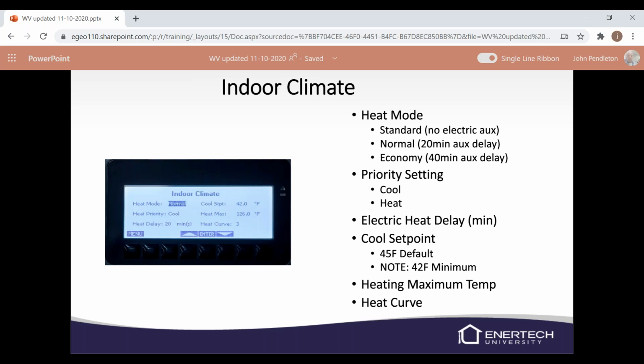You can actually go in there and adjust your electric heat delay to a different setting than those 20 or 40 minutes if you'd like. That's totally up to you. Your cooling set point, I probably wouldn't mess with it too much. 42 is about the minimum we want to see, and we recommend 45. Here you can adjust your heat curve without going back through your startup wizard. And then it'll also list the heat max set point as well here.